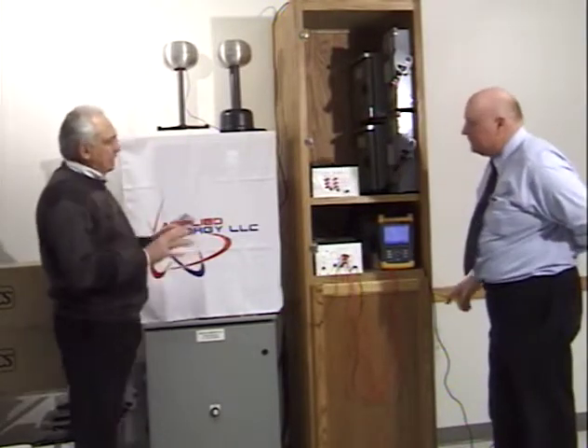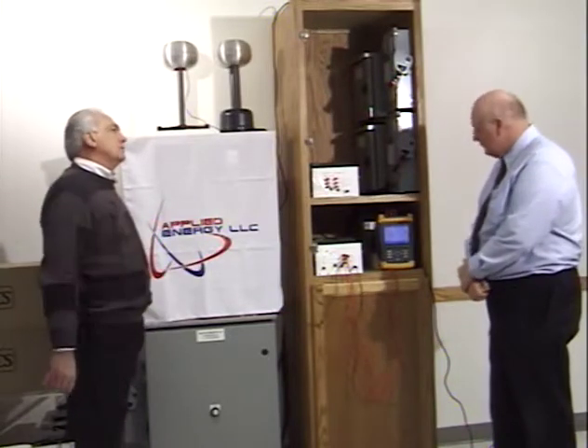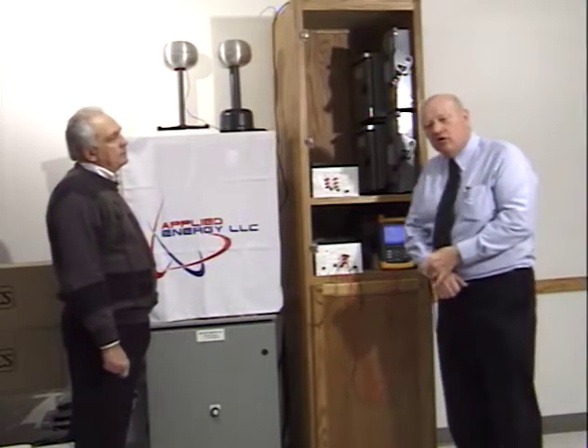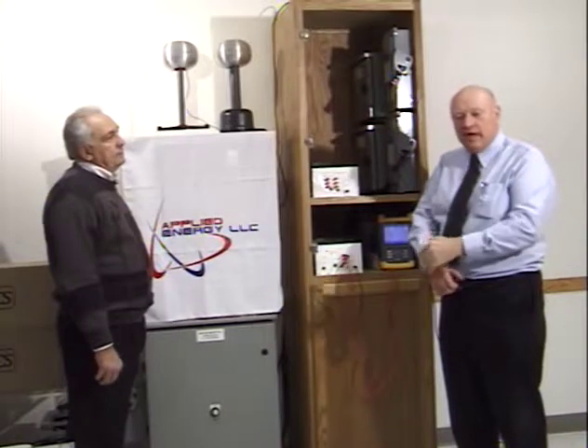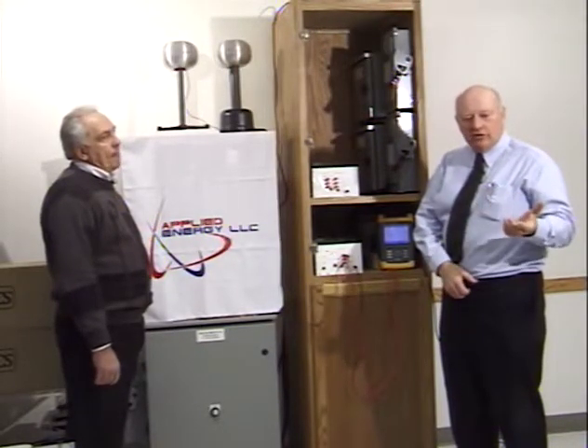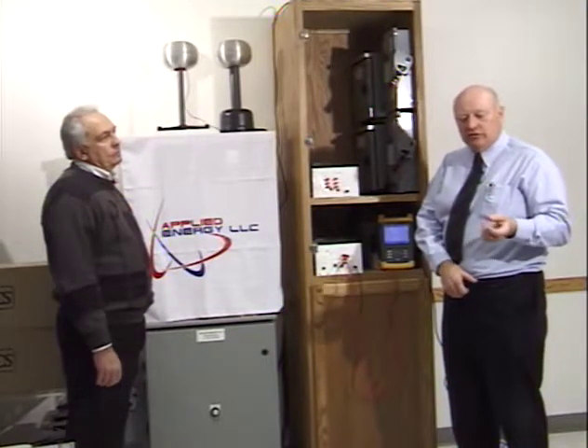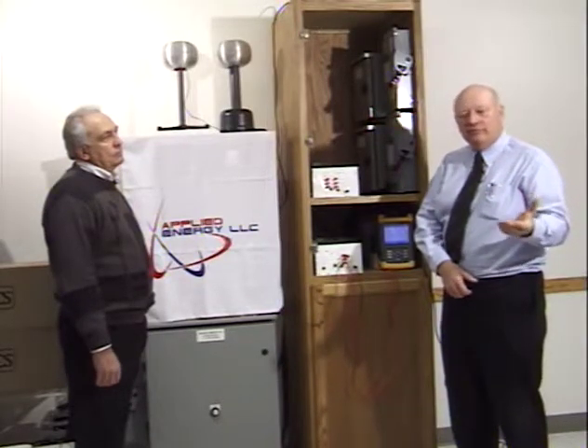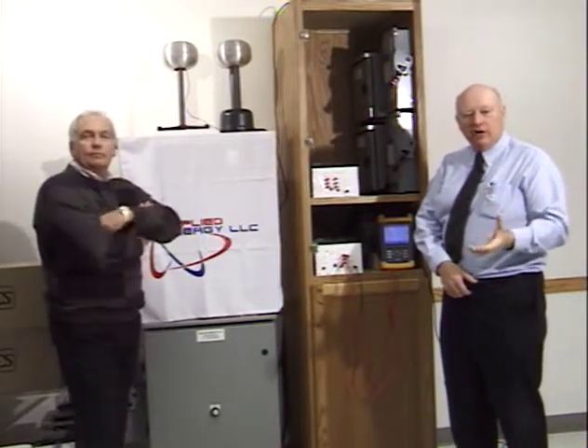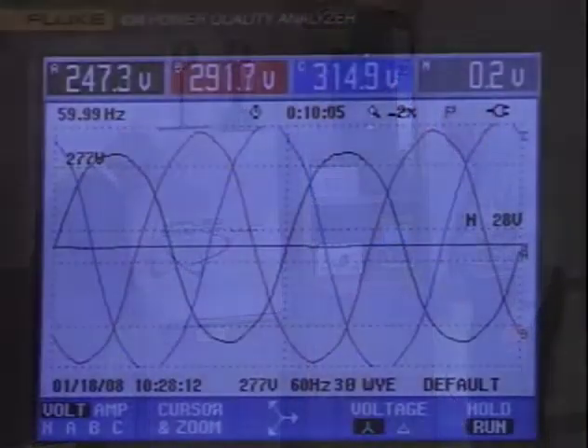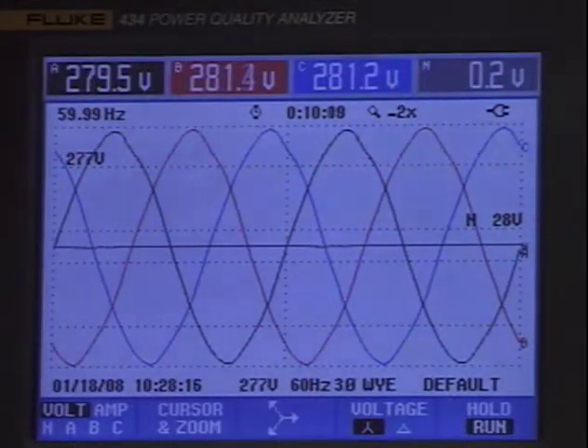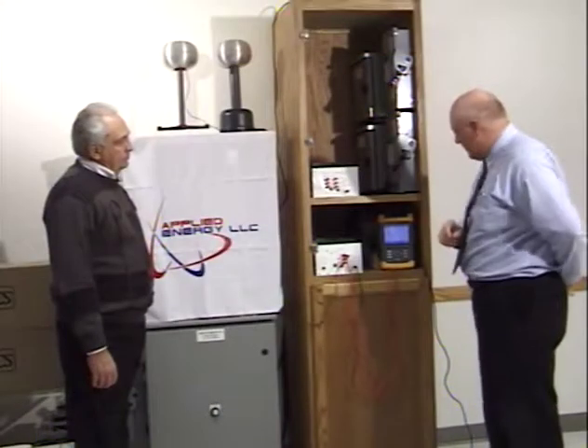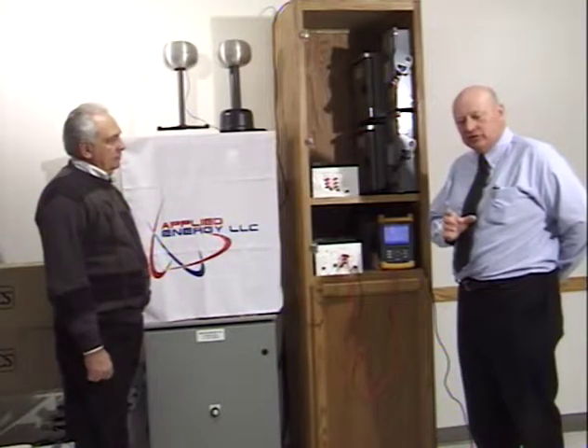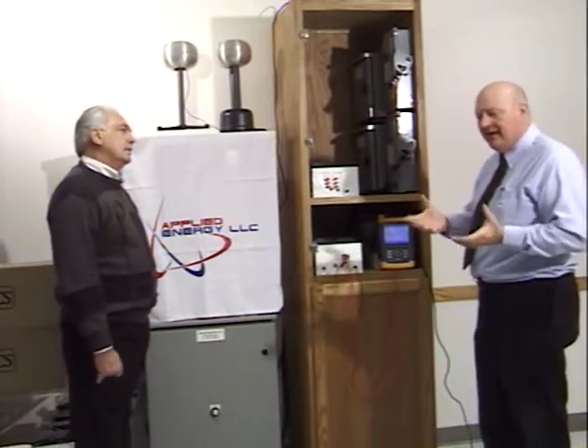Well, Bill, in a facility, what, if any, operational problems would that imbalance cause? If you have more than a 10% imbalance, that'll cause adjustable frequency drives of various brands, types, and models not to function. It can cause other issues, but the biggest issue is with unbalanced voltage feeding motors, motors can run hotter. So shortened motor life is one operational effect of having an unbalanced voltage. Turn this on. Now we have 279, 281, and 281, or actually 280, 281, and 281. So we're extremely close to being exactly the same voltage. So in addition to balancing the phase voltages, we do not require anything else to protect the system.